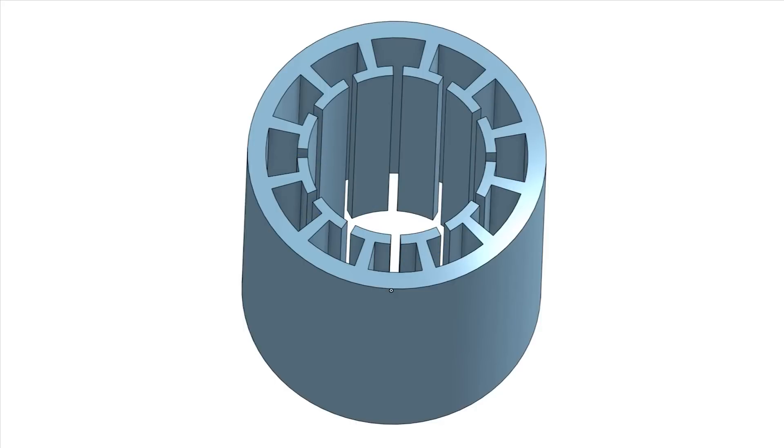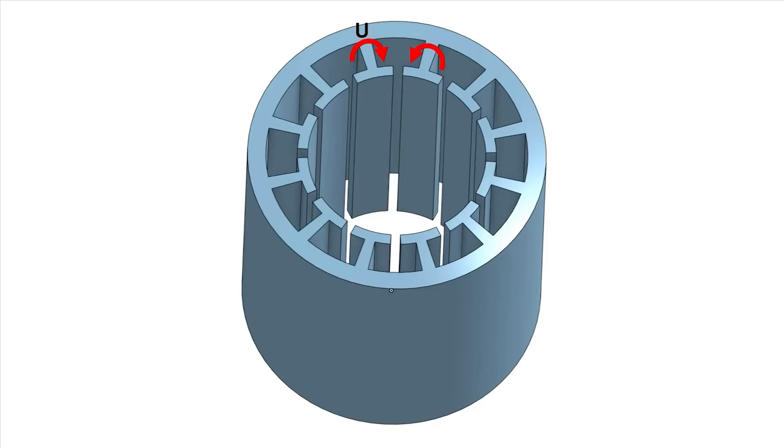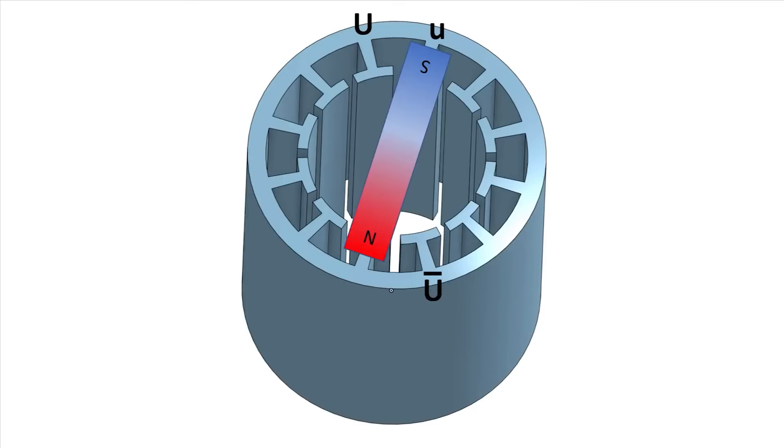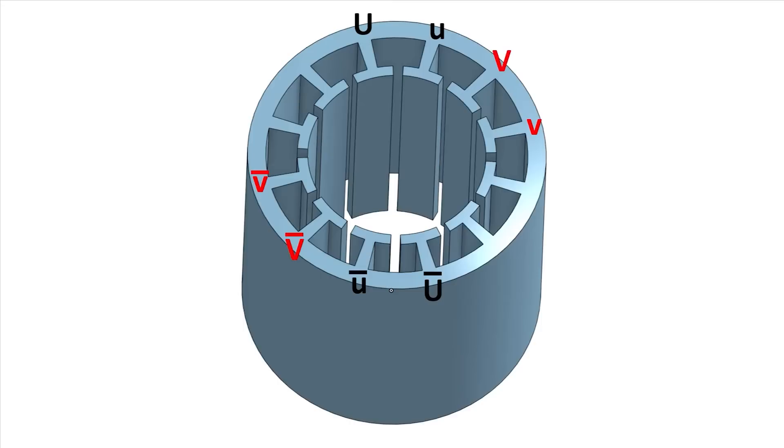If one pole is wound in a clockwise direction using the U wire, the one next to it is wound counterclockwise with the same wire to create that coupling of the magnetic fields. That gives us that side-by-side magnetic effect. Let's label this pole U and U-bar and this one little u and little u-bar indicating its reverse round. Likewise, V and W are done the same way.